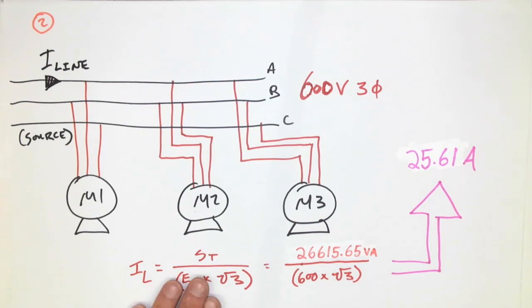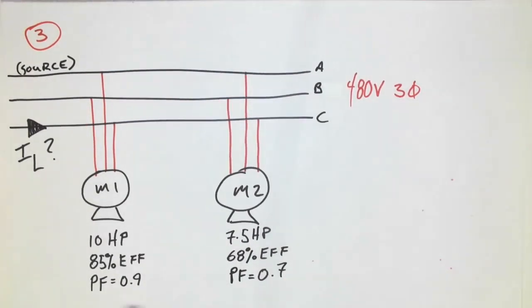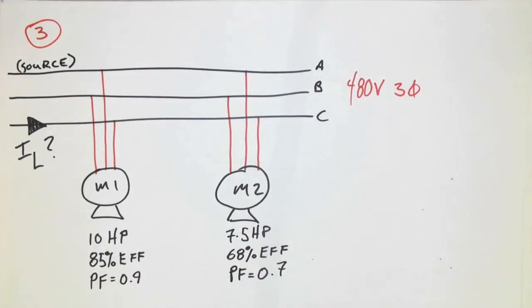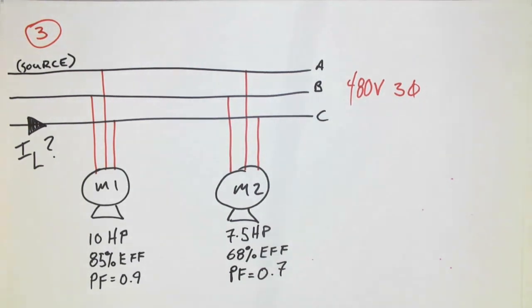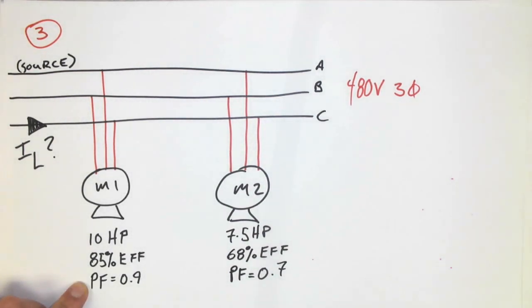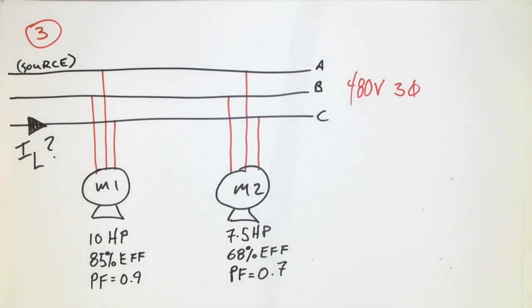Let's look at a third example. The third example is a 480-volt three-phase system with two motors — 10 horsepower and seven-and-a-half horsepower — along with some percent efficiencies and a power factor. Keep in mind that percent efficiency and power factor are two very different distinct items; they are not the same thing. Let's expand on that first and then we'll solve the actual question.